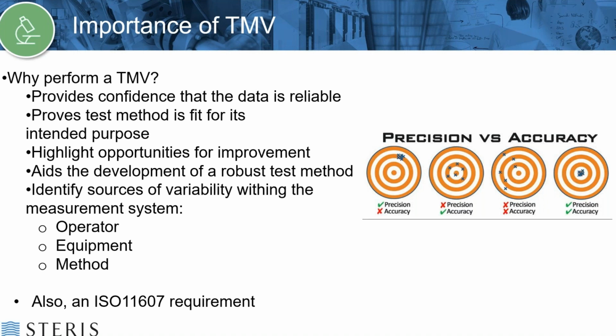I spoke about error. Typical sources of error originate from the operator, from the equipment used for testing, and also the method. And the test method validation facilitates the identification of the error sources. And once you mitigate those sources, it helps prove that the error has been minimized.